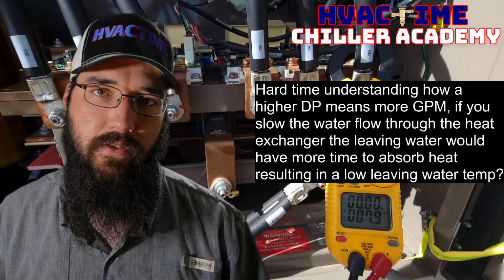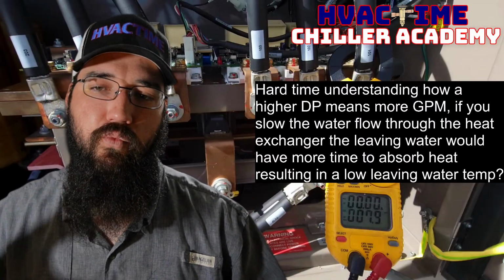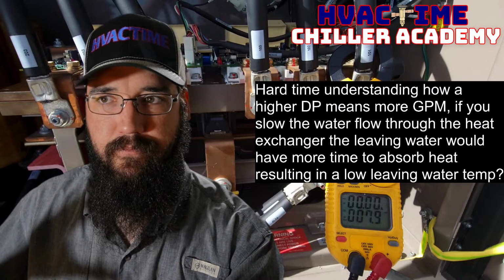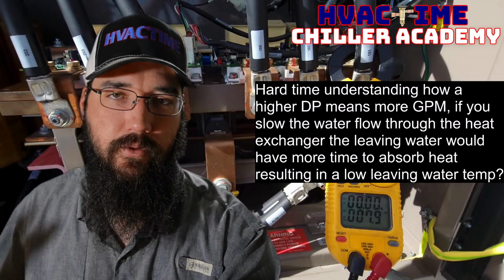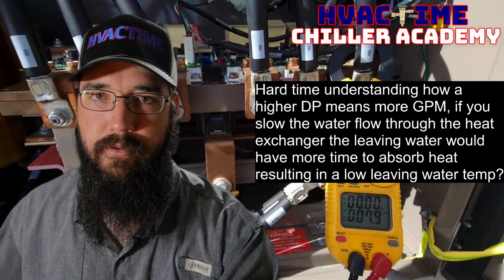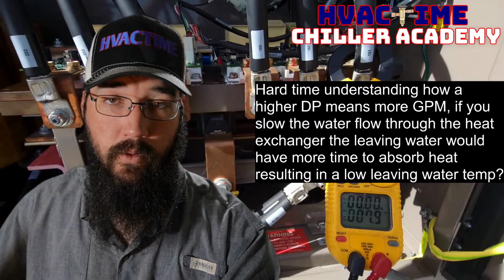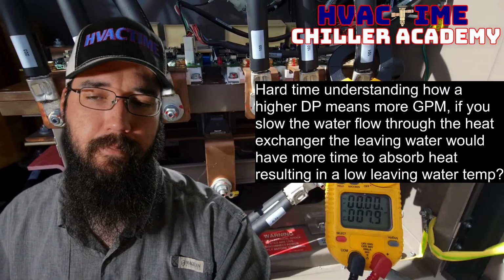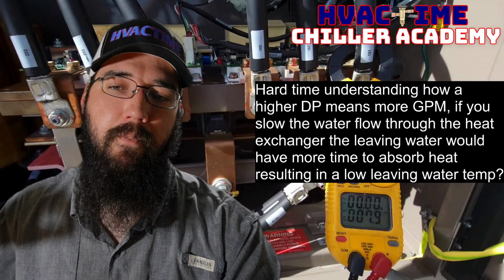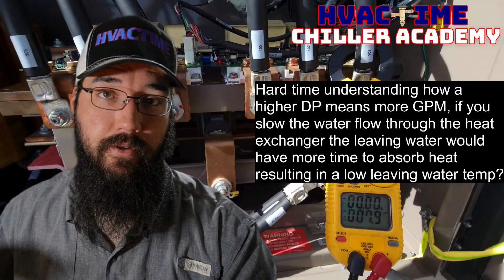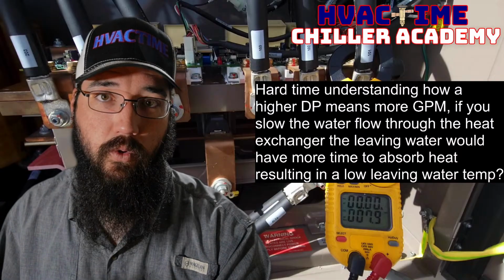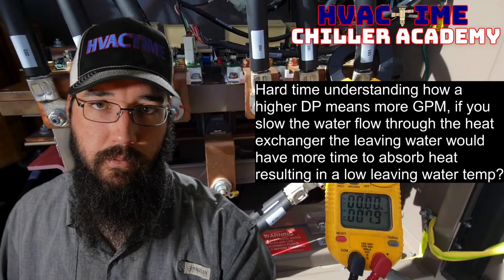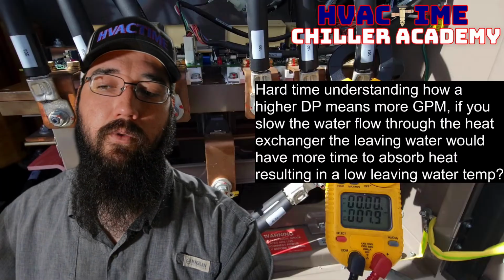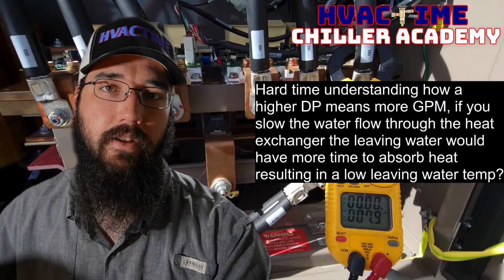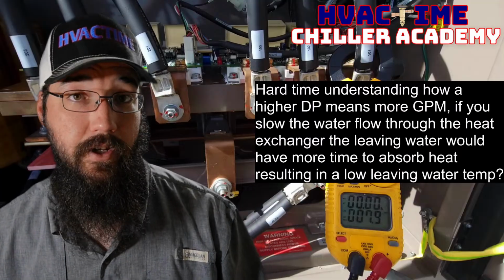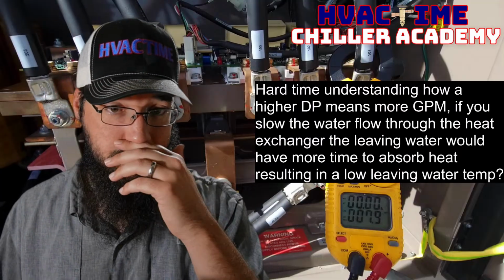The big core concept there is getting a grasp that a higher differential across the heat exchanger, evaporator, condenser, either or, does mean a higher GPM. And that will influence our temperature differential. Those do have a correlation, because how fast the water moves does impact how much approach is needed to achieve the rate of heat exchange that we need to be successful.